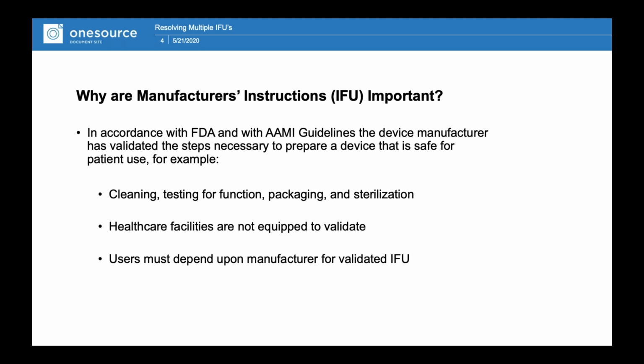historically, that's what happened. In the past, we didn't have IFUs, and we screamed and yelled at the AAMI committees and said, hey, FDA, we need cleaning and we need sterilization instructions in order to reprocess these items. And we kind of stopped there. We didn't give further guidance as users. So the FDA required it in the 510K process, and the manufacturers went out there and did all their independent testing. And then we had all these crazy cycles all over the place. 4 minutes exposure, 10 minutes exposure.